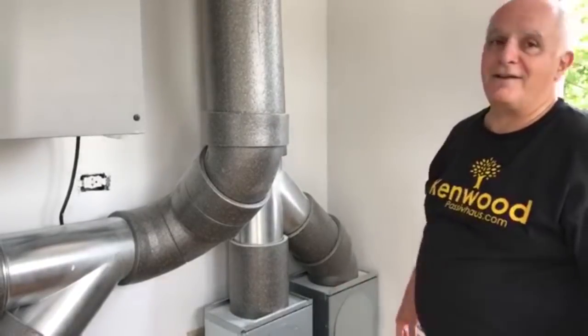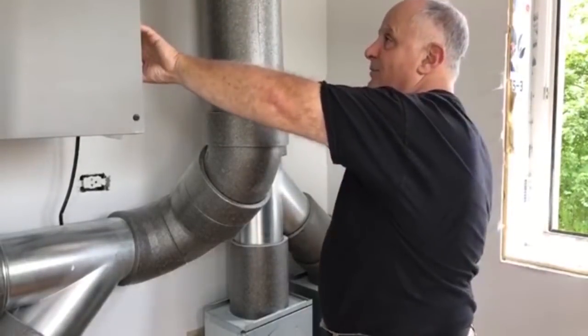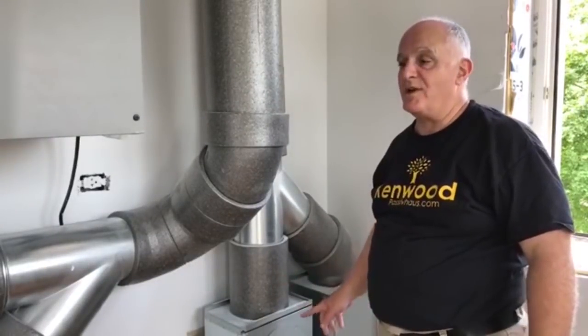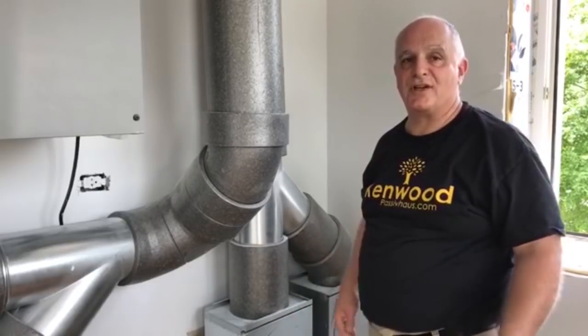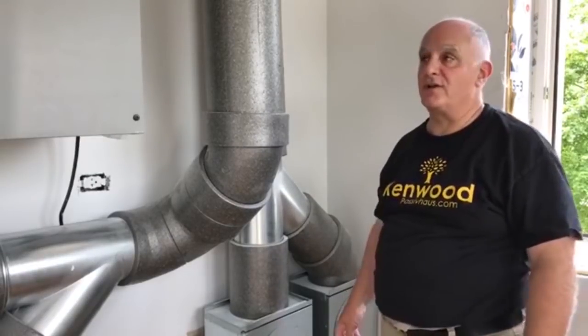So now incoming air makes its way through the Comfo 550 and then gets distributed through these 12 tubes. But when it's distributed, it's pushed through a MERV 13 filter, taking out well over 90% of the dust, pollen, airborne bacteria, and so forth. It then is extracted continuously from kitchens, bathrooms, closets, mechanical rooms, and so forth. Comes up here, goes to this side, and then it goes out over here.